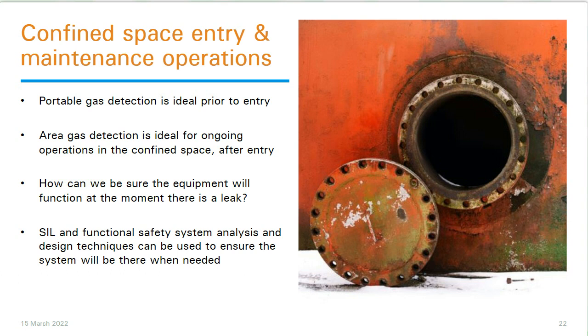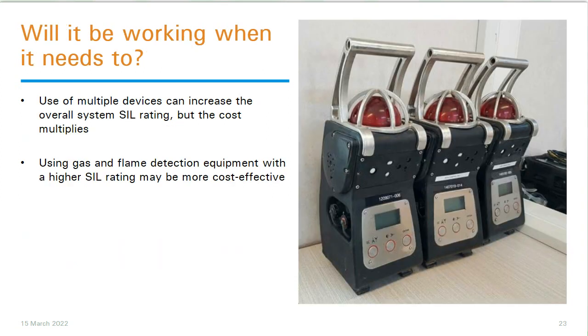And again, the SIL rating of that portable or area gas detection equipment is very, very important to consider and make sure that it is appropriate for the risks that are being taken by the maintenance team. Here are some area gas detectors, very, very typical for use during maintenance operations around toxic or flammable gases, and in particular in confined spaces. And again, if we want to increase the SIL rating of such equipment, we can, for example, use multiple devices. We can use 2 or 3 devices together, and if one of them isn't working, then we rely on the other being working at that particular moment in time to increase the SIL rating, to increase the probability that it's going to be working when we need it to be working.